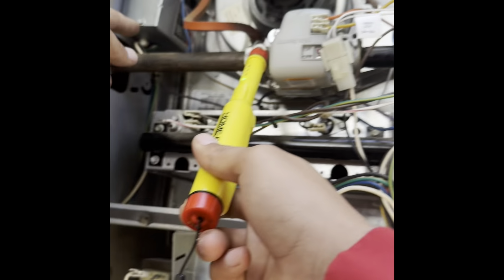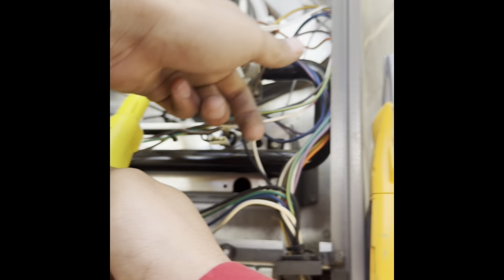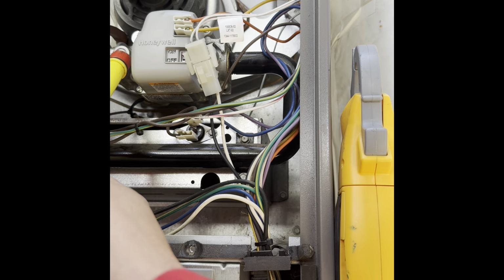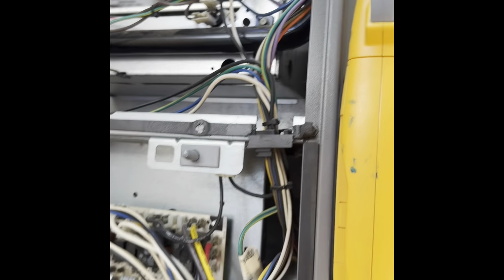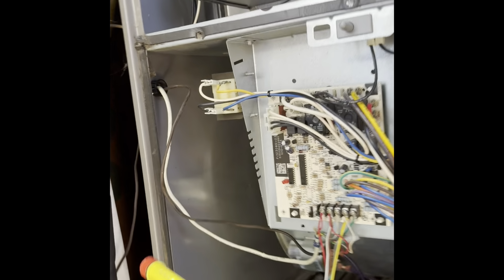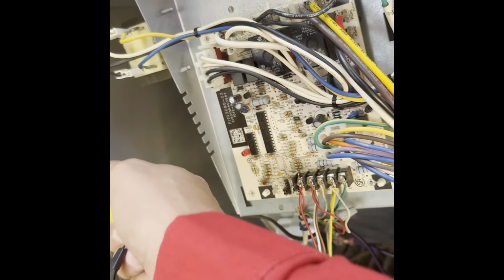So these are the screws that we use to check gas pressure. It will be an incoming gas pressure and the outlet gas pressure. There's no leaks there. There's no leaks here. There's no leaks there at all either. So this gas valve is pretty good. I don't see any gas leaks. The next thing we want to check is the flex itself, the disconnect flex, to see if there's any leaks there.